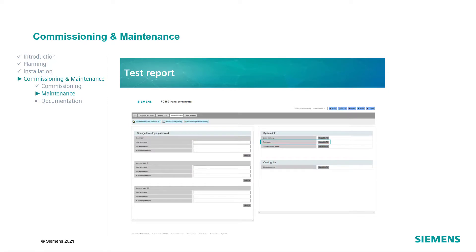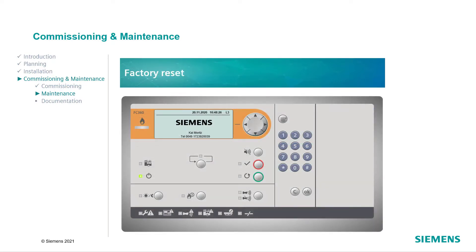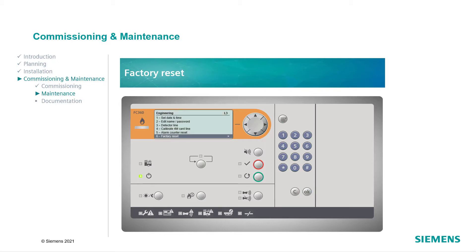The test report listing all tested devices can be downloaded in the Administration tab of the Panel Configurator. For the factory reset of the panel, open the menu on the FC360 panel and navigate to the Engineering option. Confirm with OK, then go to Factory Reset and confirm with OK. Press OK again to start the factory reset. All data will be deleted from the panel and the panel starts up again. When the restart has been completed, you can select if the auto-configuration should be done now or at a later time.